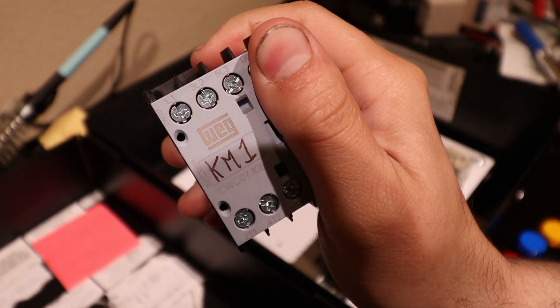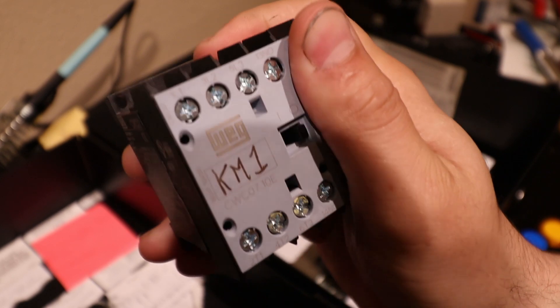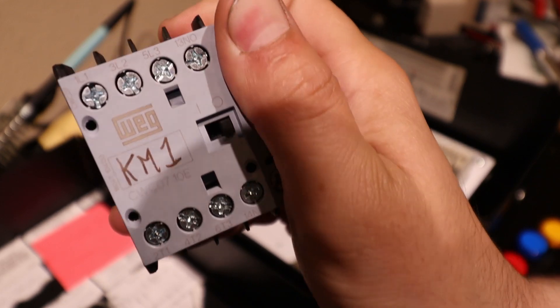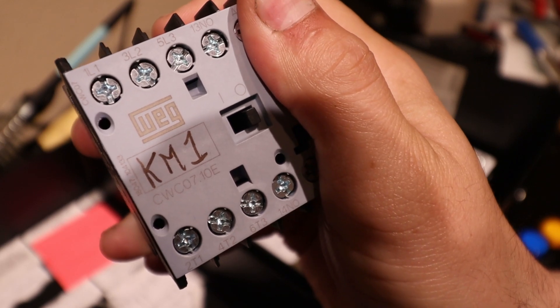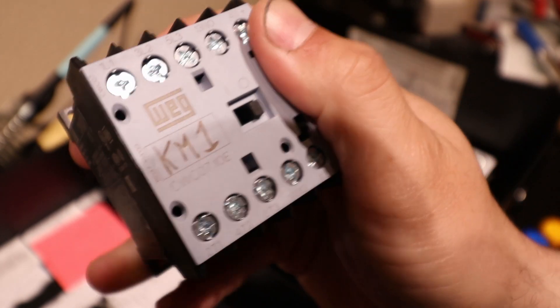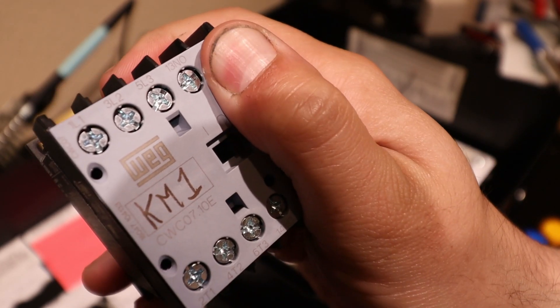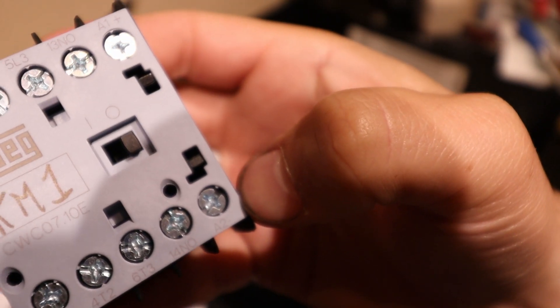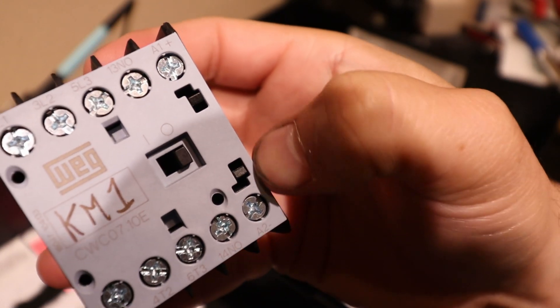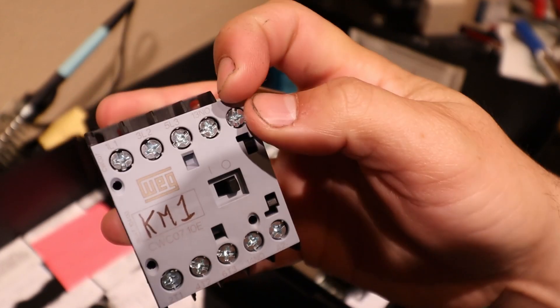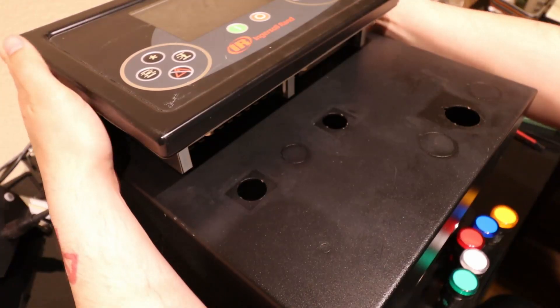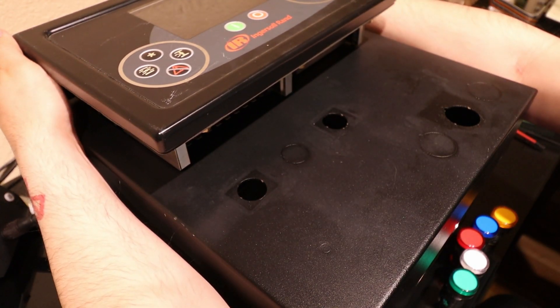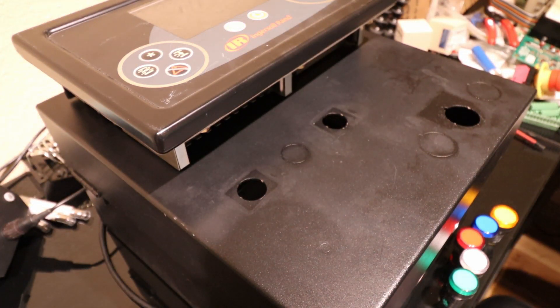The three contacts shown right here are for closing the contacts between the three phases meant to start the main motor. The fourth one is the normally open contacts, this is an extra bonus feature on this contactor specifically meant to close normally open contacts when the contactor pulls in. The A1 and A2 shown all the way on the right of the contactor are the 120 volt solenoids that actually makes the contactor pull in when sent 120 volts to the contactor from the controller, and those are normally on top of the contactor in a large industrial type contactor.